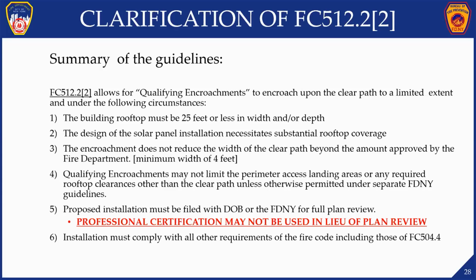The encroachment may not reduce the clear path by more than 2 feet or reduce the clear path to less than 4 feet wide. So the clear path must always be at least 4 feet wide. If it's 3 feet and 11 inches, then it's no longer considered to be acceptable. It doesn't meet the guidelines for this qualifying encroachment.